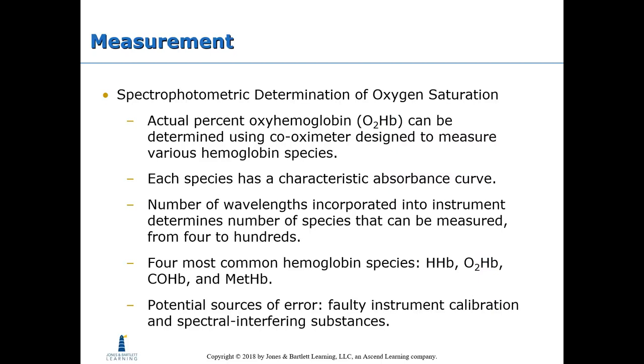The spectrophotometric determination of oxygen saturation: the actual percent of oxyhemoglobin can be determined using a co-oximeter designed to measure various hemoglobin species. Each species has a characteristic absorbance curve, and the number of wavelengths incorporated into the instrument determines the number of species that can be measured — from four to hundreds, with four being the most common. Potential sources of error include faulty instrument calibration and spectrally interfering substances.